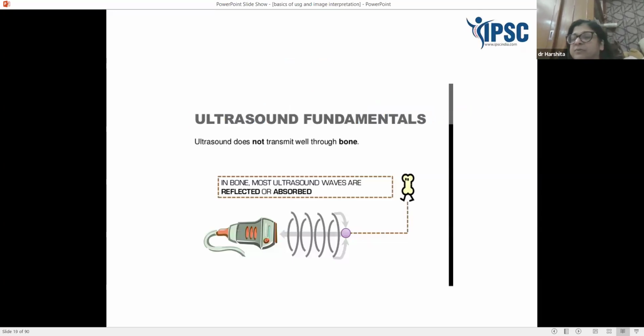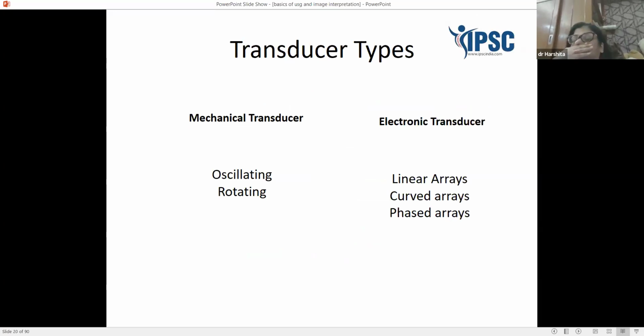This we have already discussed. Ultrasound beams do not travel through the bone. Now, coming back to the probes. The probes are of two types according to their make. Earlier, we had all mechanical probes. Now, what are mechanical probes? The piezoelectric crystals are mounted on a machine which either oscillates or rotates. With this oscillation or rotation, the piezoelectric crystals used to get triggered and emit ultrasound beams. But now mechanical probes are almost getting replaced by the electronic probes, in which the electrodes get stimulated and cause the piezoelectric crystals to vibrate and produce ultrasound beams.